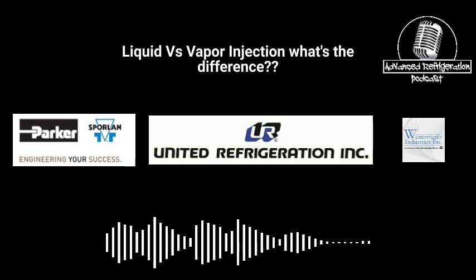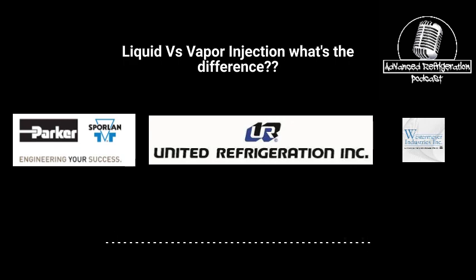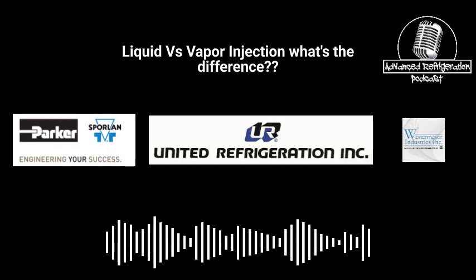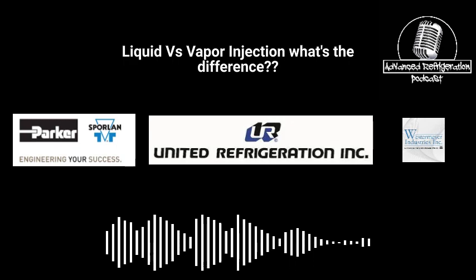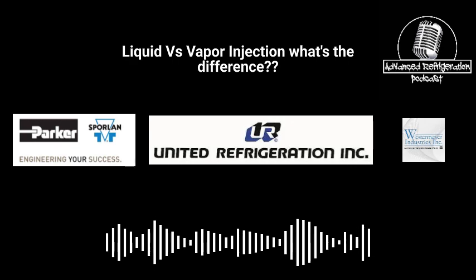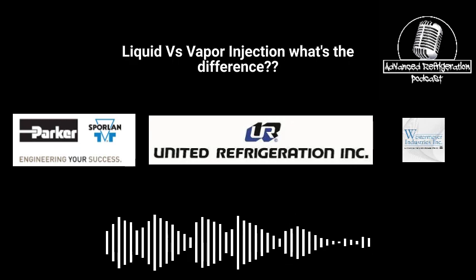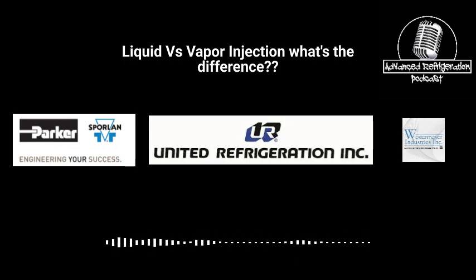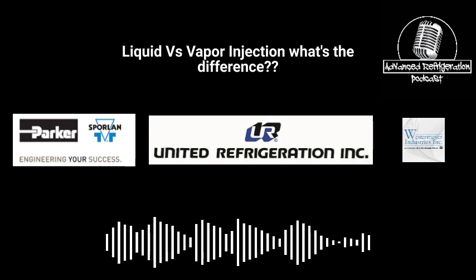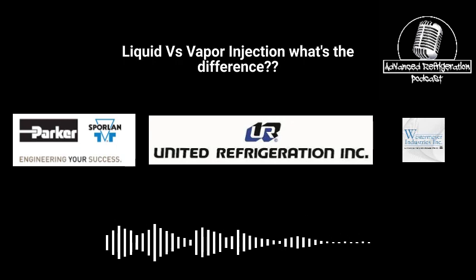So do you do the same thing that I do? Basically, have it at your midpoint. If you're trying to control 50 degrees and you are typically on a non-glided refrigerant, you'd have that thing rolling at around 40 degrees saturated, right? If you're dealing with a glided refrigerant, you want to make sure your EPR set point would theoretically be at your midpoint. So if you're 40 degrees for your vapor, but yet 30 degrees for your liquid saturated at that particular pressure, that's essentially being at a 35-degree saturated, which would be good for trying to control like a 45-degree outlet on your subcooler. So just take that into effect when you're trying to set those up.